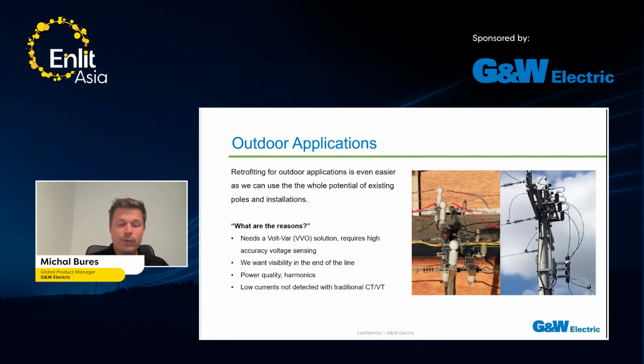So why do we want to upgrade the existing application? What are the reasons? For example, we need a volt-var solution, which requires high accuracy voltage sensing. We want visibility at the end of the line, which can be provided very easily by sensors. We want to measure power quality and harmonics because somewhere in the grid is a new photovoltaic farm or wind turbines. And maybe we are a utility which is not able to detect low currents with traditional CTs and VTs. So sensors are the solution that can help us.